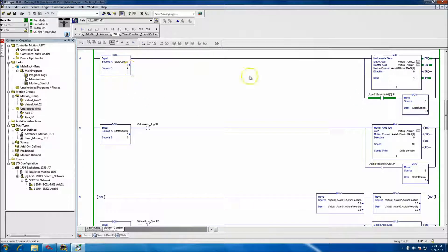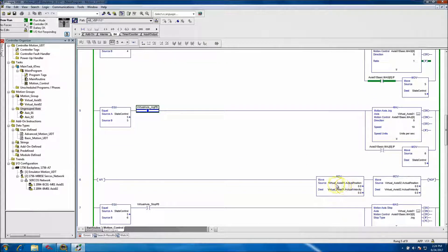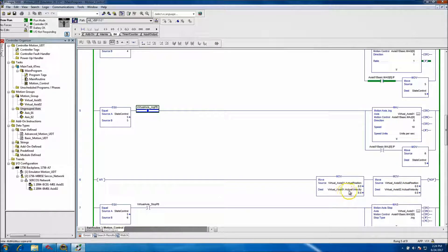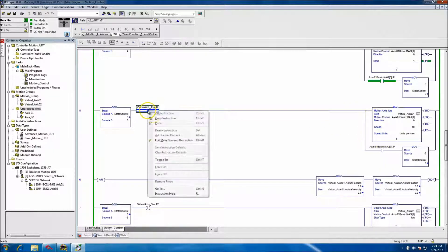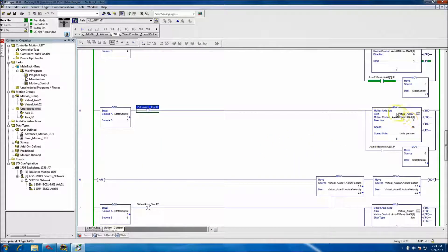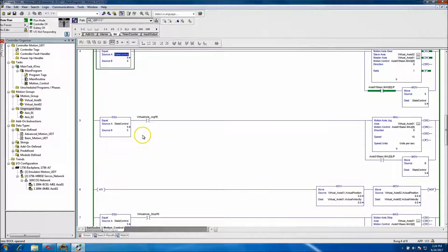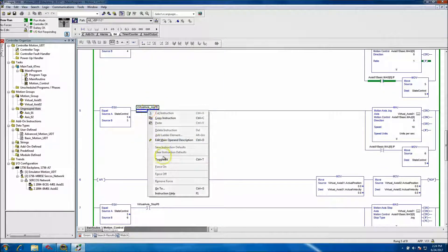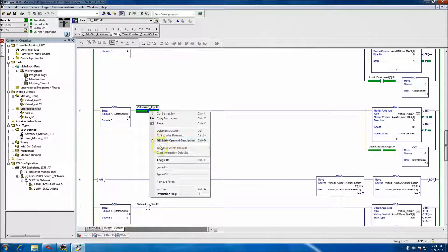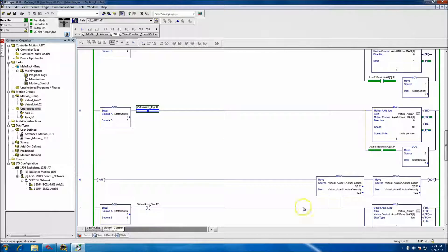Now that they're geared together, confirmed by the IP bit, we've transitioned from state 4 to state 5. You can see that Virtual Axis 1 and Virtual Axis 2 actual position and velocity are not moving because no jog command has been issued. If I simply toggle this bit, Virtual Axis 1 will jog and both axes will jog together because they are geared. Let's go ahead and show that example — I can immediately toggle it off because it will continue jogging until we issue a stop command.